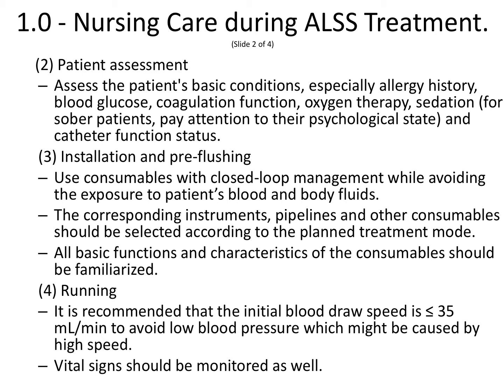3. Installation and pre-flushing. Use consumables with closed-loop management while avoiding exposure to patients' blood and body fluids. The corresponding instruments, pipelines and other consumables should be selected according to the planned treatment mode. All basic functions and characteristics of the consumables should be familiarized. 4. Running. It is recommended that the initial blood draw speed is less than or equal to 35 milliliters per minute to avoid low blood pressure, which might be caused by high speed. Vital signs should be monitored as well.